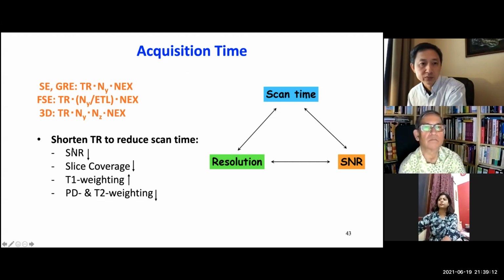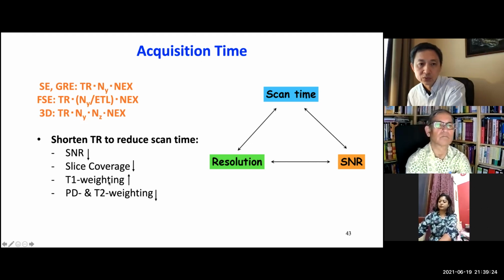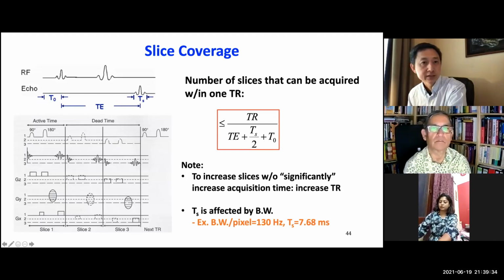But what else will be caused when we reduce TR? The SNR will be reduced because there is less time for T1 to recover. Slice coverage will be less. It will be good for T1 weighting, but not good for T2 weighting. So we need to understand all of those from the basic physics. This is my last slide. Slice coverage is also important. Many times we want to cover a lot of anatomical region, but what limits the slice coverage? We need to understand how much time is required to image one slice. That's the minimum time required to acquire one slice.